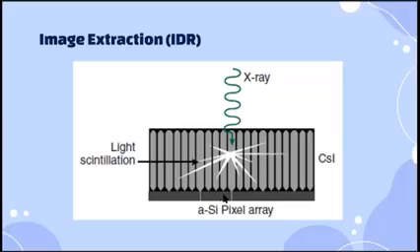Okay, so when the amorphous silicon detects the light, no, in the detector, the light is converted into an electrical charge, okay, which is done by the photodiodes within the detector element. Okay, and then the electrical charge again is stored in the capacitor, and then we will wait for the voltage to be on the appropriate amount, and then the TFT gate opens na naman for the DEXEL to be read out. Okay?